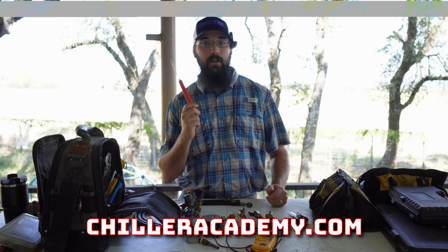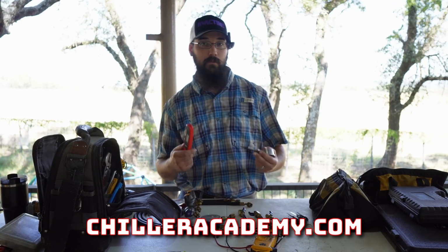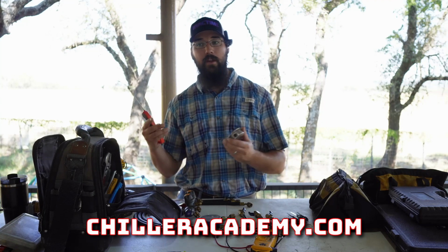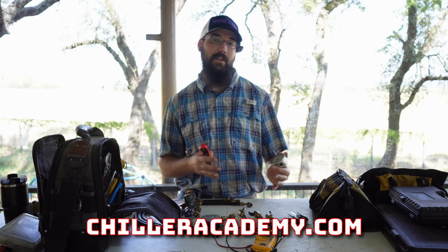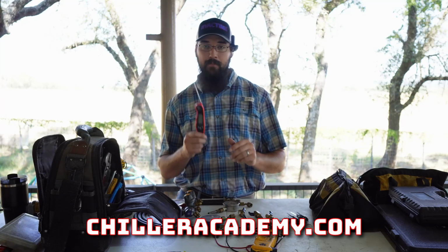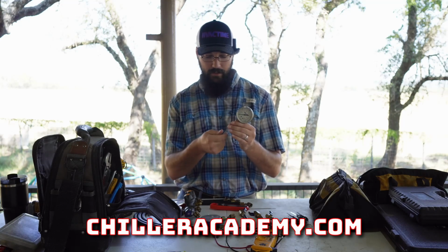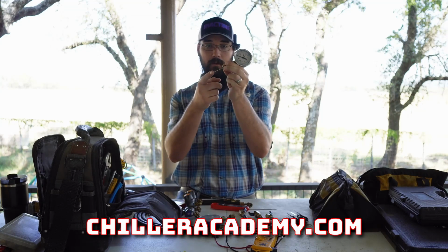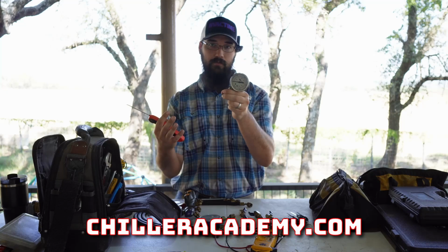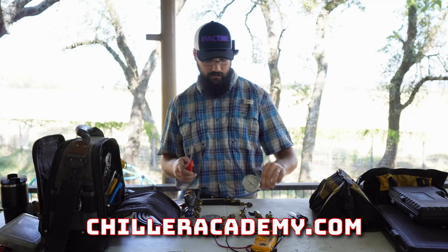Your standard thermometers do not fit in a PT port. Now, I've referred to these in the past as Pete's plugs or Pete's ports. I've actually learned recently, in the last few months, that the proper name for a Pete's, which is actually PT, is pressure temperature. I didn't know that until somebody pointed it out to me, so I appreciate that. But these fit in there. So a set of water gauges, I'll cover this more in a second, but this is an official Pete's needle, okay? You can see how small it is. Now they also make a little bit of a larger one for a larger style of PT plug, but this is the official standard needle that you'll see on most systems.